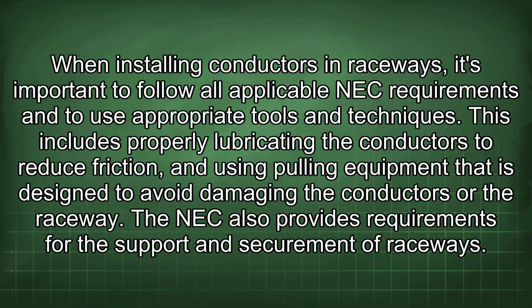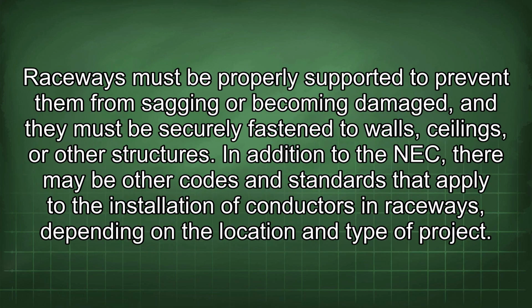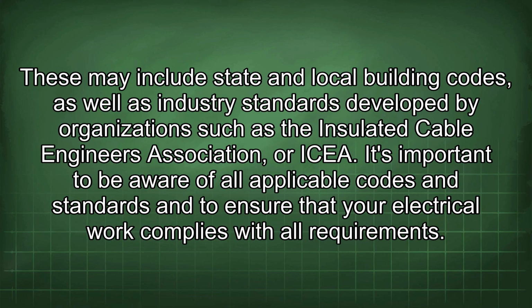The NEC also provides requirements for the support and securement of raceways. Raceways must be properly supported to prevent them from sagging or becoming damaged, and they must be securely fastened to walls, ceilings, or other structures. In addition to the NEC, there may be other codes and standards that apply to the installation of conductors in raceways depending on the location and type of project. These may include state and local building codes, as well as industry standards developed by organizations such as the Insulated Cable Engineers Association, or ICEA.